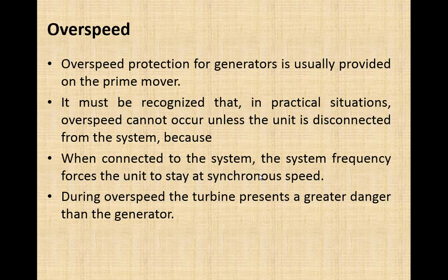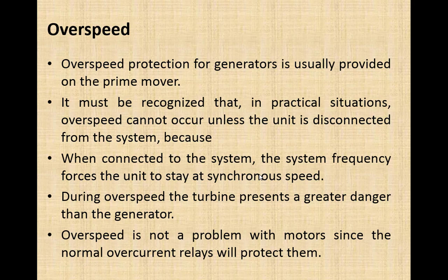Now we discuss overspeeding of motors. Overspeed is not a problem with motors since normal overcurrent relay will protect them. If we are driving a motor through a motor drive that could control its torque and speed, the motor may be operated above the synchronous speed that is defined by the number of poles and frequency. By changing the frequency using the motor drive, speed can be increased. But if load is also high and speed is higher than the synchronous speed, the motor will draw a very high current. So overload protection could detect this problem and provide protection against overspeeding.